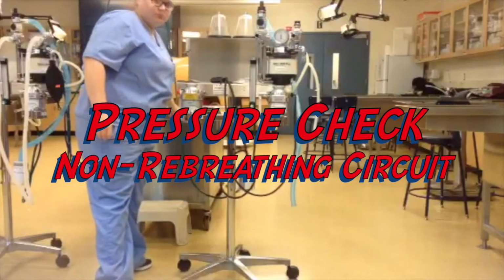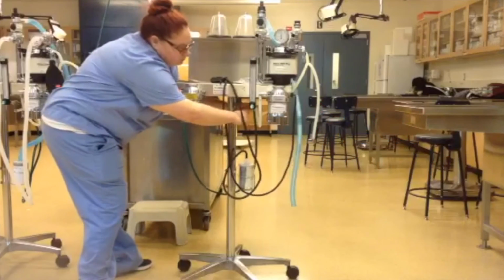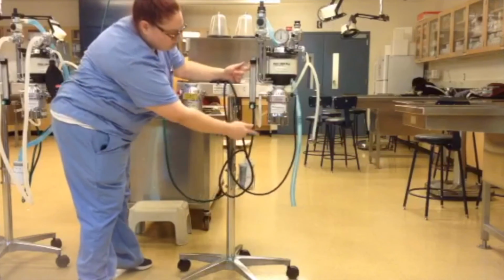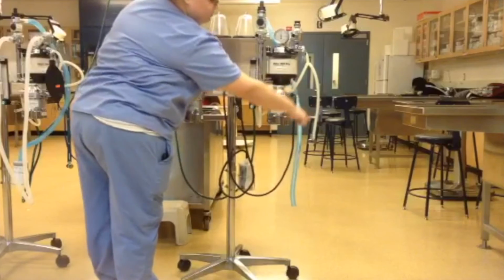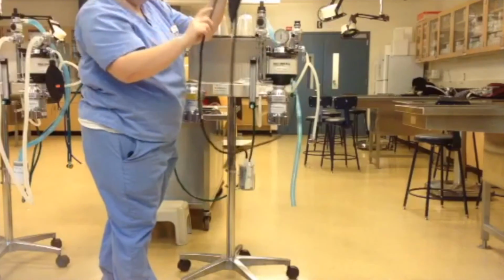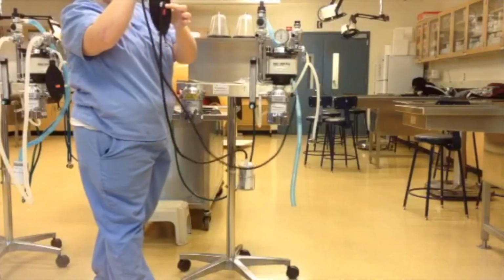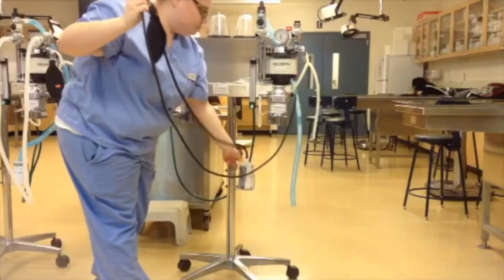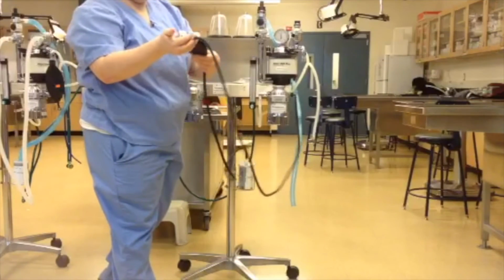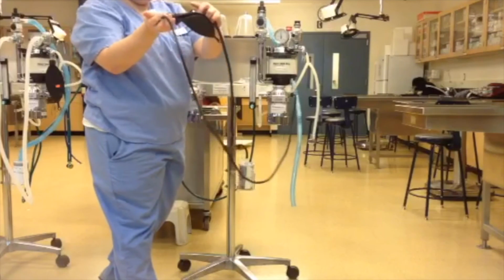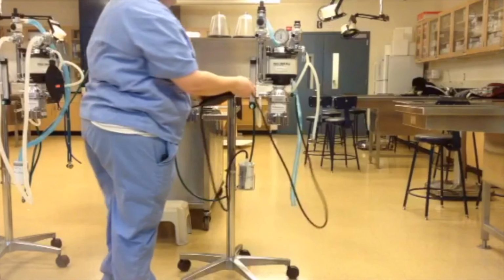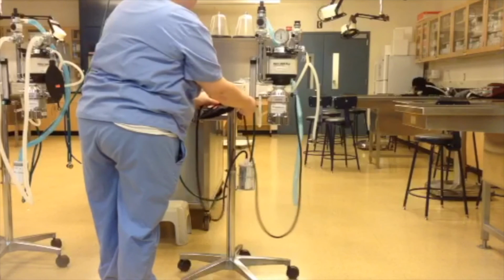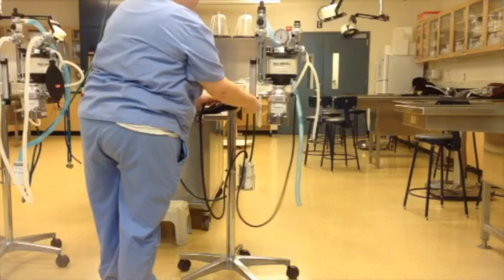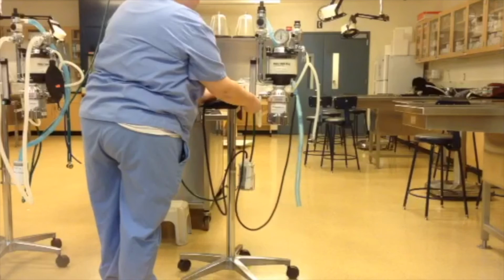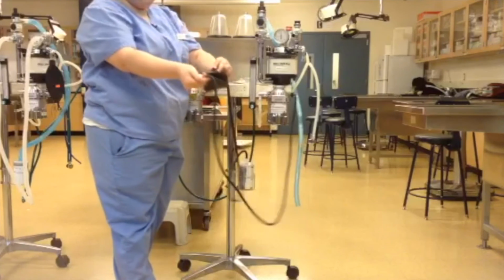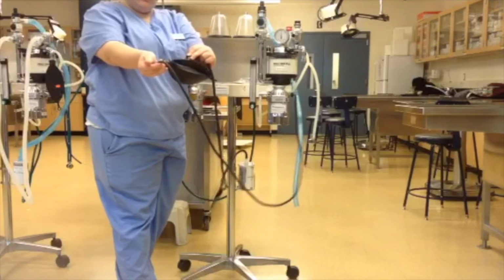Now we'll be pressure checking for non-rebreathing. We have our oxygen connected to the flow meter. We're making sure that our outlet is connected to our non-rebreathing system. I have my hand placed against the connector, and now there's also a pop-off valve on the actual reservoir bag. Then I turn the flow meter up all the way, and then I let the flow of oxygen flow through the reservoir bag completely till it's full.